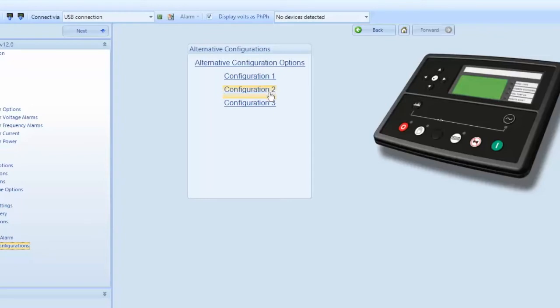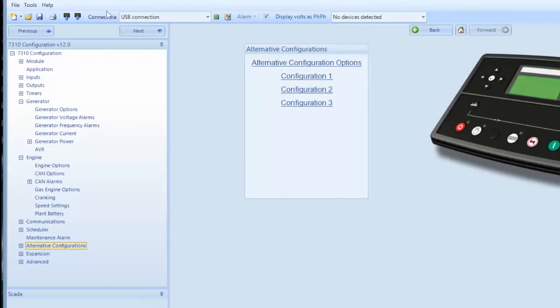When you go into one of the configurations again, you will have access to generator and engine parameters. Once you have made the changes in the selected configuration, you save that configuration and click on the button to the left of the read from module icon called write to module as indicated.